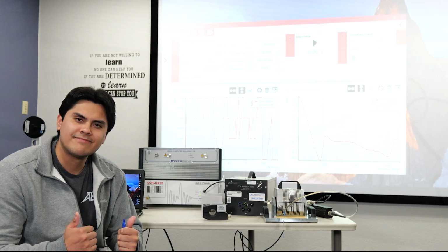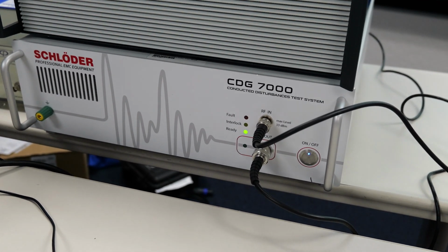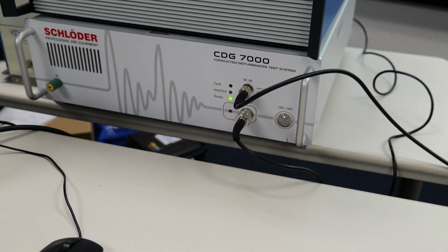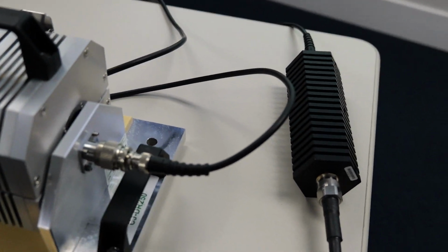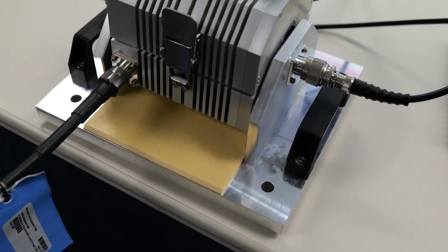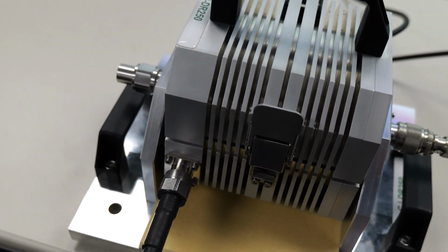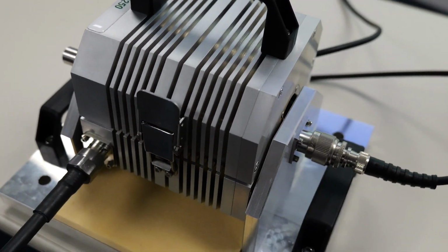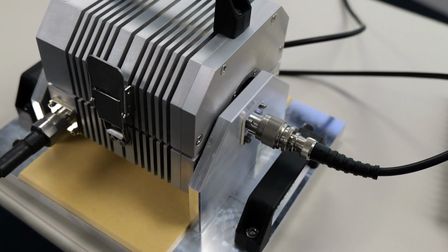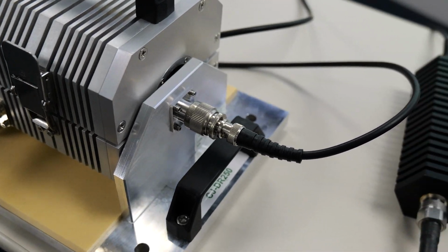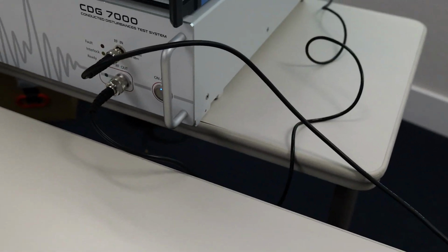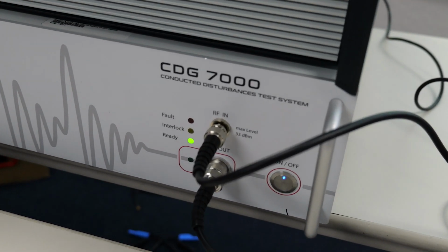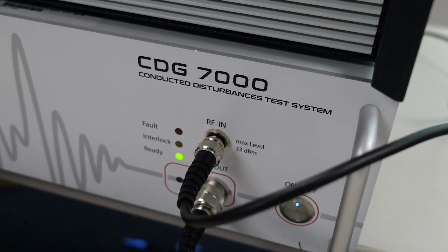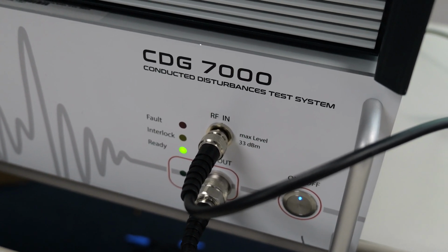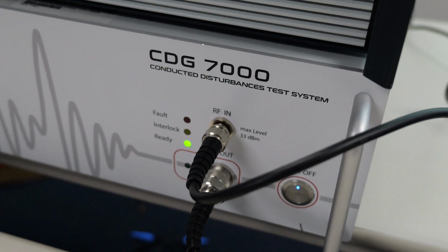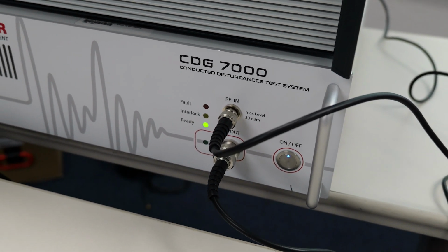So let's get started. Currently I have my CDG 7000 output going to my 6 dB attenuator, which then goes into my bulk current injection probe, which I have an RF load on one end, and I have the RF cable that goes to my power meter input going to the front of my CDG 7000. Just keep in mind every power meter input has a max drive level, so make sure you start off low and don't overdrive because you can damage your very sensitive test equipment.